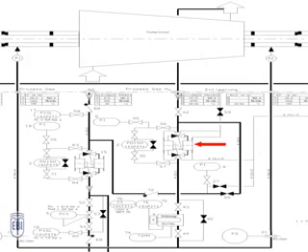The function of the filter is controlled by measuring the pressure drop with the differential pressure gauge. There will be an alarm of the pressure gauge if the filter is polluted. The standby filter has to be activated and the filter cartridge can be exchanged. Experience shows that the filter cartridge should be changed at least once a year.